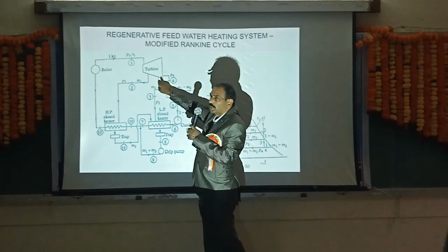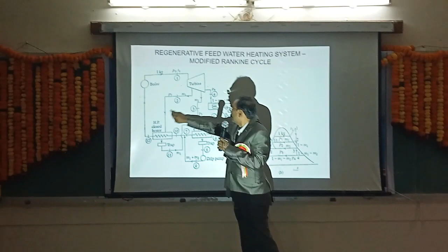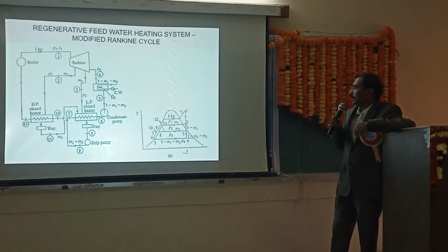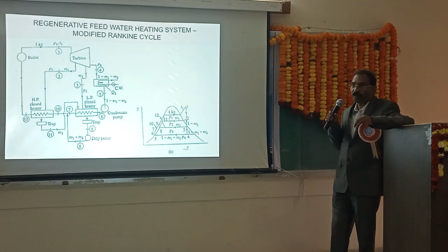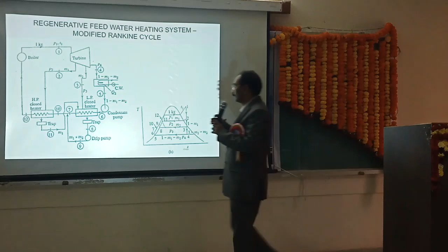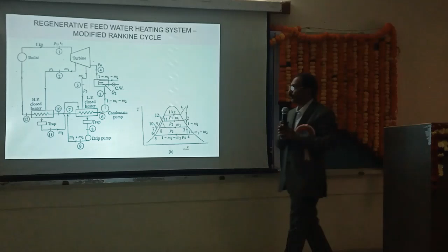This is the place where we improve the Rankine cycle: regenerative heating of the feed water. From the turbine, we take the extraction steam in the middle, before it goes to the exhaust pressure, and that is fed to the heaters, HP heaters, LP heaters. Through these the feed water will be preheated and the load on the boiler will come down. By the time the feed water reaches the boiler, it will be preheated to the saturation point. So the heat requirement for the steam will come down, and thereby the efficiency of the cycle improves.